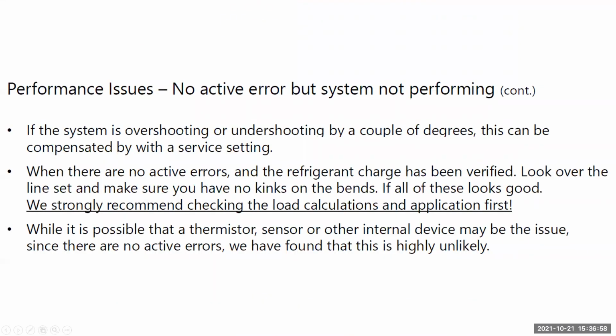So performance issues, but not getting an active error code. Refrigerant charge is the main one you want to check. And we discussed how to get that: pull your refrigerant out, check it against your data plate, and add in for any extra line set. If it's low, you have a leak. It could be in your coil, could be just a line rubbing. Somebody could have drove a screw through the line set.